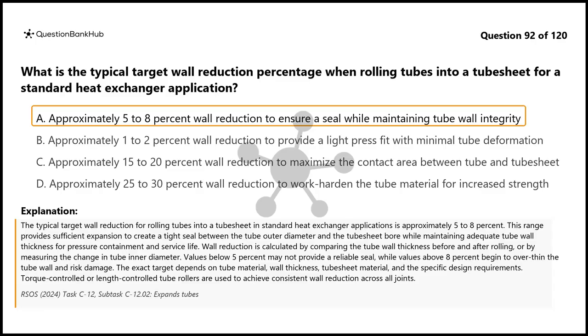Wall reduction is calculated by comparing the tube wall thickness before and after rolling, or by measuring the change in tube inner diameter. Values below 5% may not provide a reliable seal, while values above 8% begin to overthin the tube wall and risk damage. The exact target depends on tube material, wall thickness, tube sheet material, and the specific design requirements. Torque-controlled or length-controlled tube rollers are used to achieve consistent wall reduction across all joints.